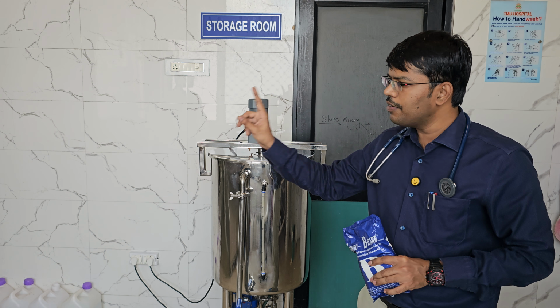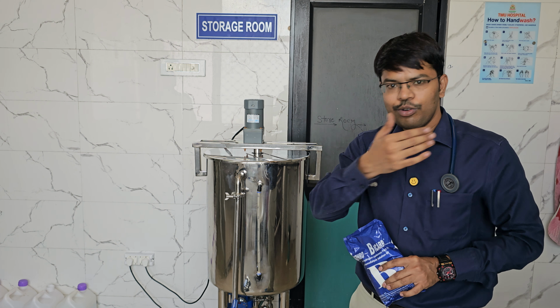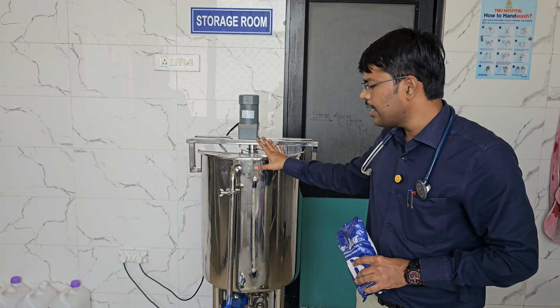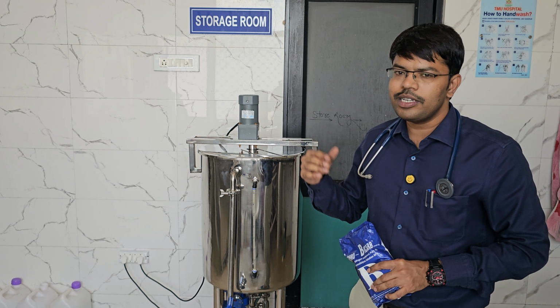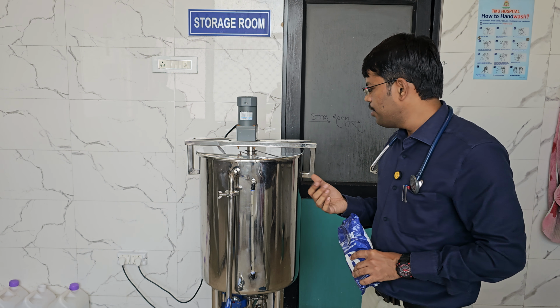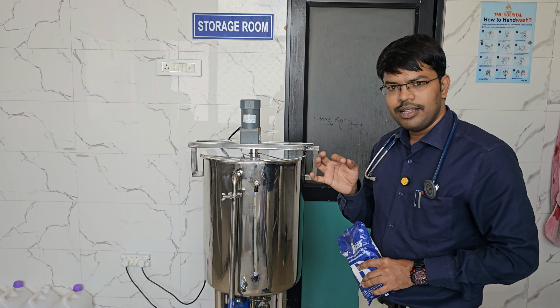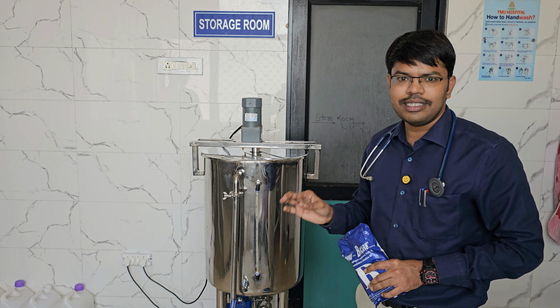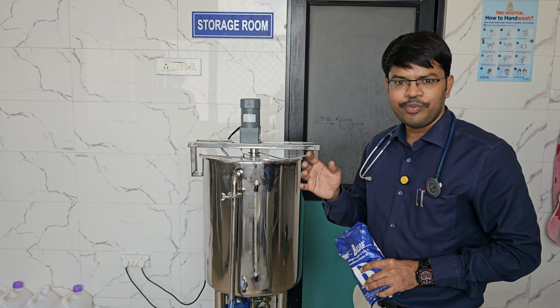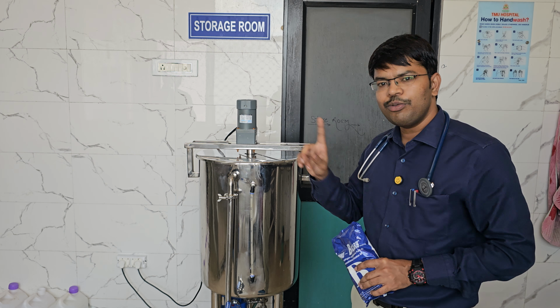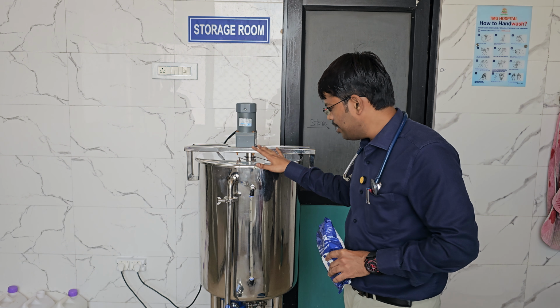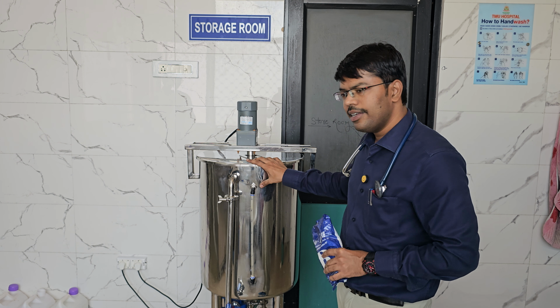The same RO water that we use for the dialysis patient, coming through the line, has to be used, not normal RO, because the patient will develop a reaction if normal water is used. Dialysis-specified, quality-checked water, with low endotoxin and low TDS, has to be used. Water and powder are put in this container.